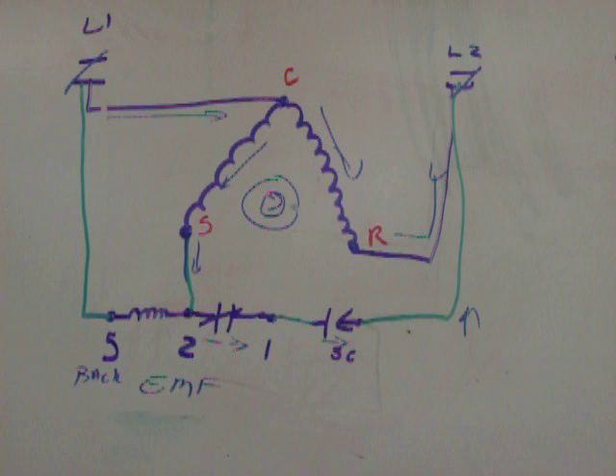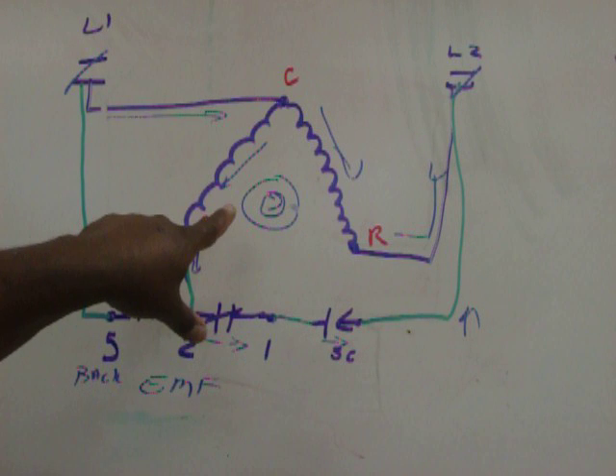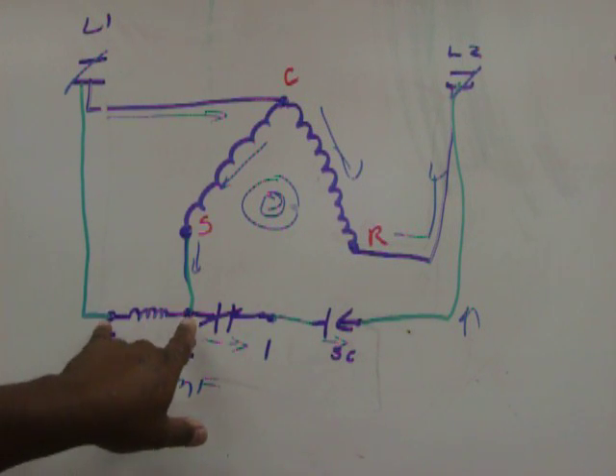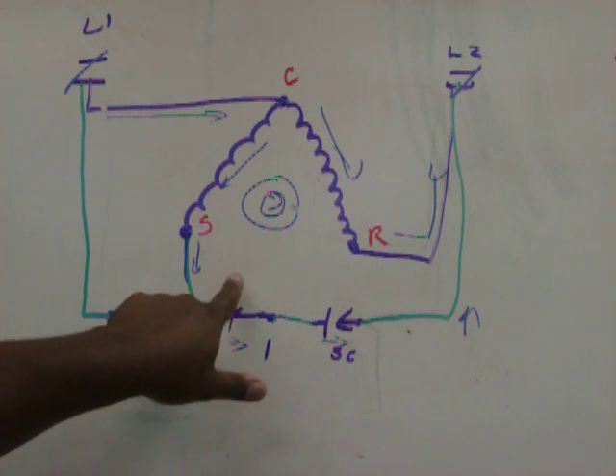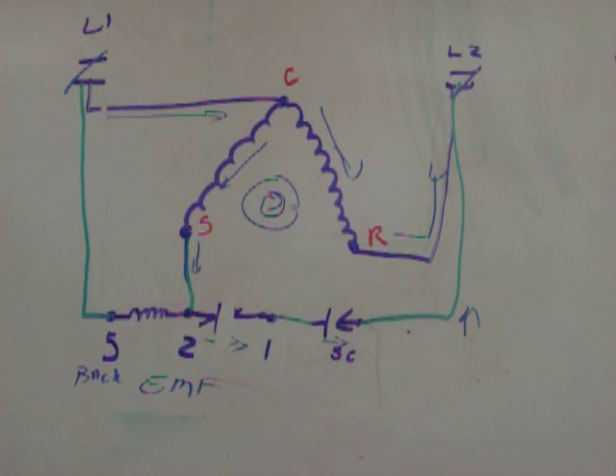And as it turns, it actually creates electricity just like a generator does. That electricity back feeds five to two. That back EMF is what energizes the potential relay. So you may have a compressor that's 208 volts, but your pickup voltage is going to be a lot higher. It may be 280, 300 volts, depends on what it's calling for. After this motor gets up to speed and running, the rotor goes to turning. You generate back EMF. It energizes five and two. When five and two is energized, the normally closed opens up, which takes the start capacitor out the circuit. And now we continue running without the start winding in there. And that's all it is to it.